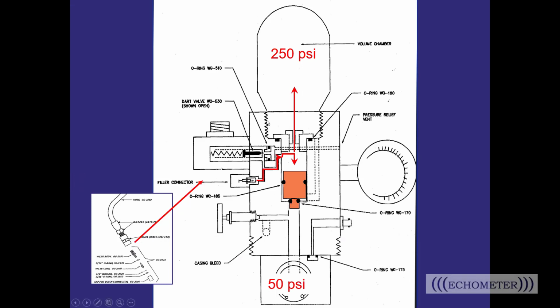So the next thing we're going to do is activate that solenoid to fire the shot. Okay, so if you're using the well analyzer, once you click fire shot, or if you're operating the wireless gun, you click fire shot. And so now that the solenoid is activated, we're sending 12 volts to the solenoid. And so what it's going to do is there's a little spring in there. It's going to activate that spring and pull that dart valve back. Okay, so currently this little dart valve here is closing off that path. When it's pulled back, that's going to release the pressure on top of the gas valve.